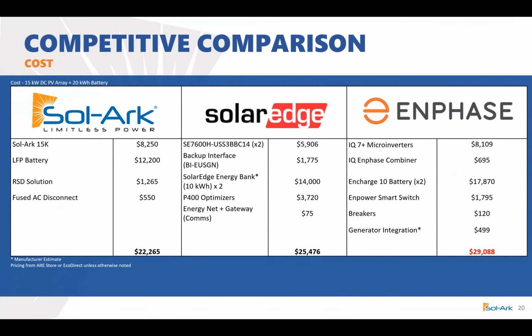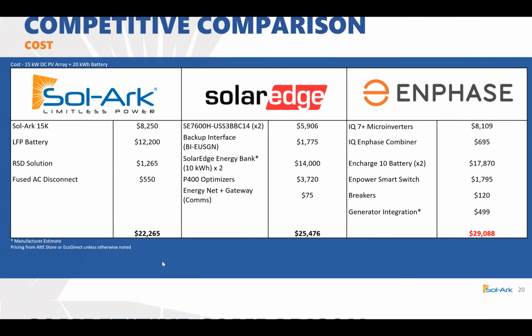Next, we'll just go on to our cost and our bill of materials. We try to keep things easy at Sol-Ark, and our all-in-one solution really does that. So instead of purchasing multiple different pieces of materials that really add up in cost, as long as you get our all-in-one model, plus around a 20 kilowatt hour battery bank, which is what we're sizing for here with the 15 kilowatt array, all we need is that RSD solution plus a fused AC disconnect, and that's all you need, compared to some of our competitors here.